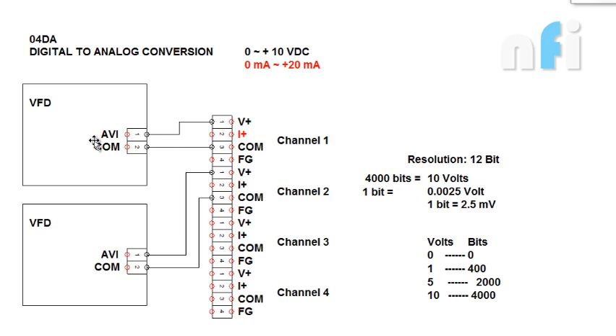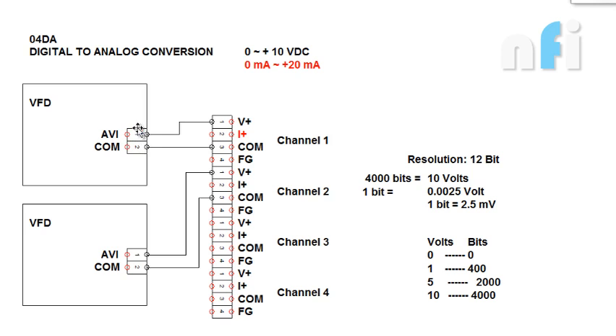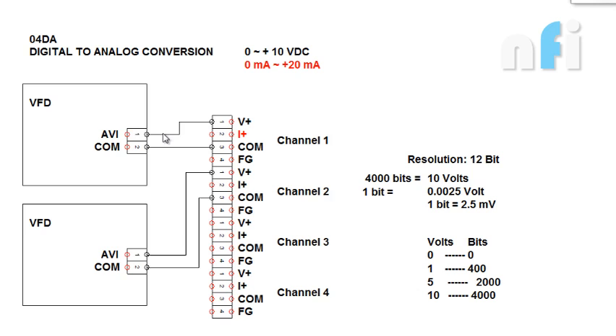So we have connected the V+ to AVI terminal of a drive. AVI is analog voltage input which can be designated by some different name in different drives. In this Delta VFD we name it as AVI. If we give the voltage ranging from 0 to 10V in this terminal, it will change the frequency from 0 to 50Hz. If we give 0V it will convert to 0Hz. If we give 5V it will give 25Hz. If we give 10V it will convert to 50Hz.